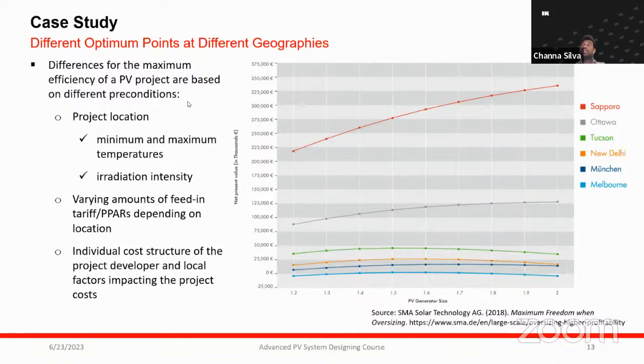Let's assume the maximum temperature is much higher compared to another location, then some energy is being lost at that particular location. So in that case, it's fine to oversize where the maximum temperatures are much higher. Likewise, the minimum temperatures. So average ambient temperature always has to be considered, and average irradiance.